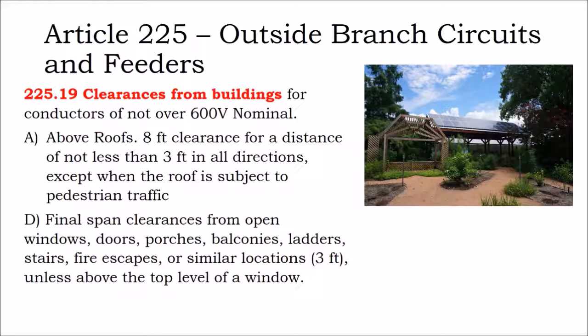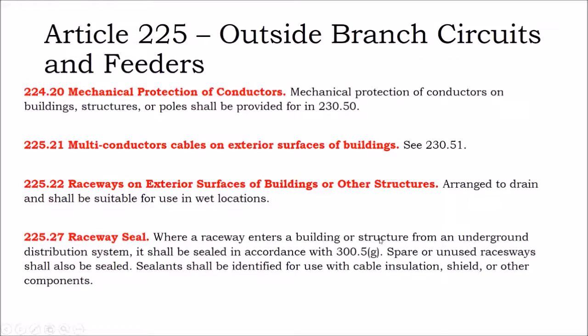But then again, if you have a 3-story tall row home and your power lines just go up to the top of the home, you're running your service conductors from the power line to the house. It's only on that top span at the very top of the unit where you can get closer to the window, to stay just on the top edge of presumably an inaccessible rooftop. So the final span, you have to stay 3 feet away from your windows and porches and balconies and ladders, unless you're at the top level of the home, at which point you can just go above the window, between the window and the top of the building wall.